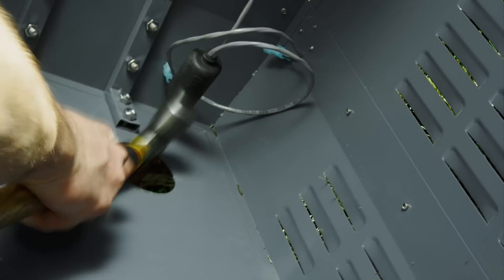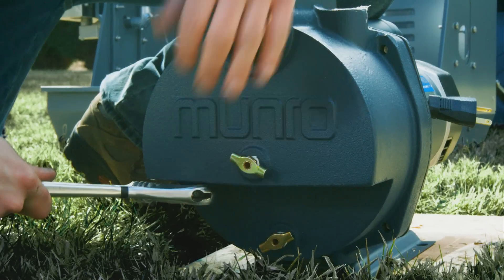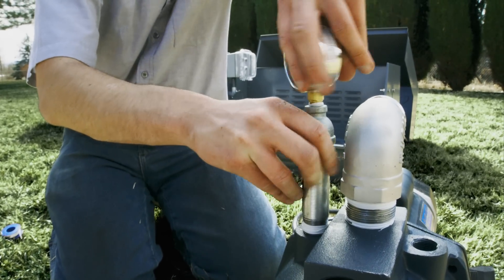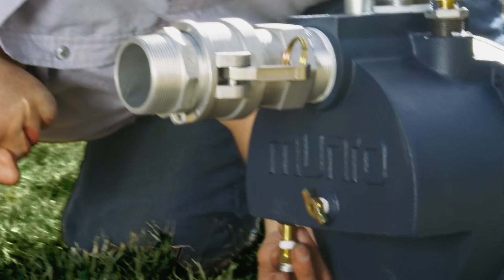Since the powder-coated stainless steel enclosure comes fully assembled, simply knock out the appropriate discharge hole and place the enclosure over the irrigation inlet. Prepare the professional-grade Munro pump by removing the protective plugs. Next, install the two-piece discharge assembly. Thread the pressure gauge assembly into the top of the pump, then install the pressure and temperature monitoring sensors.